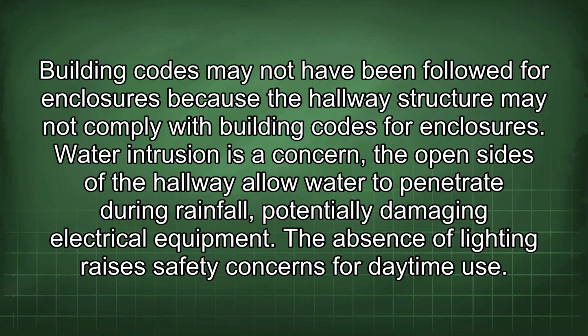Building codes may not have been followed for enclosures because the hallway structure may not comply with building codes for enclosures. Water intrusion is a concern. The open sides of the hallway allow water to penetrate during rainfall, potentially damaging electrical equipment. The absence of lighting raises safety concerns for daytime use.